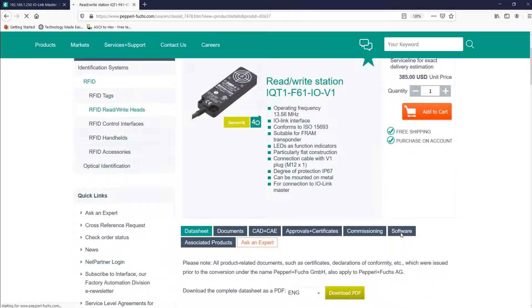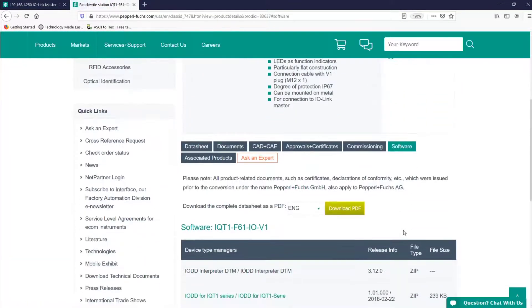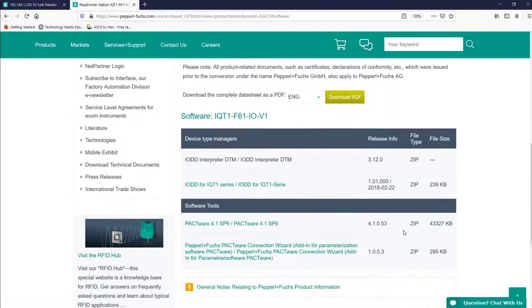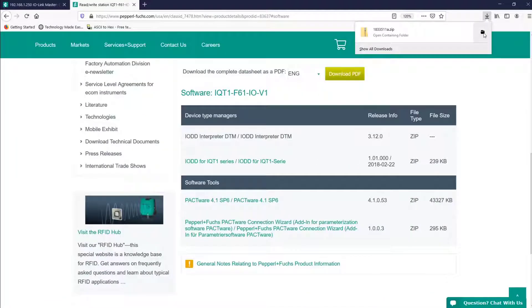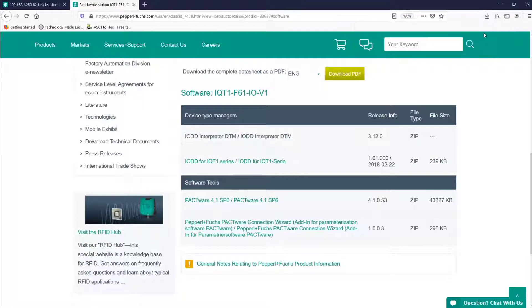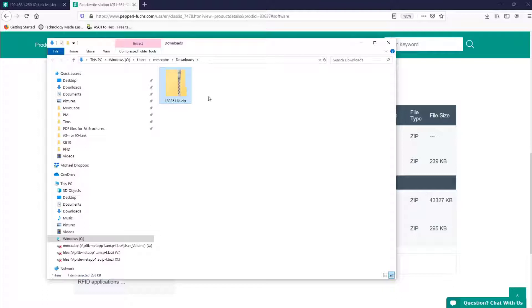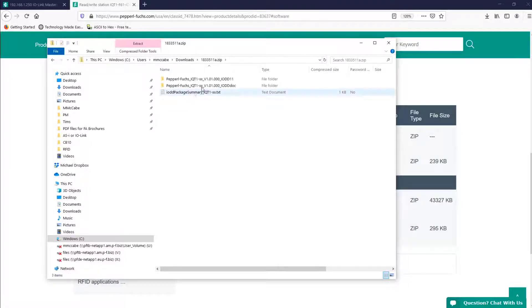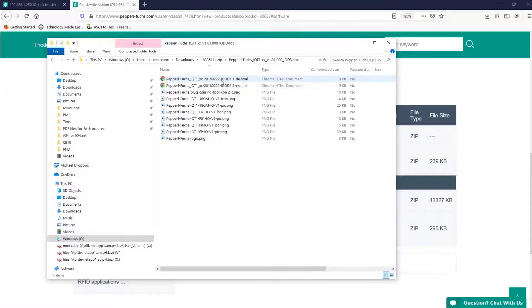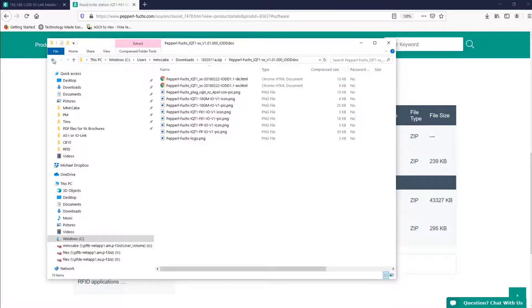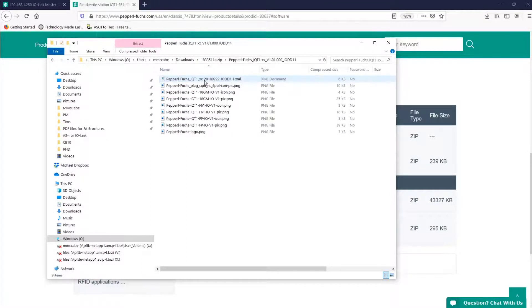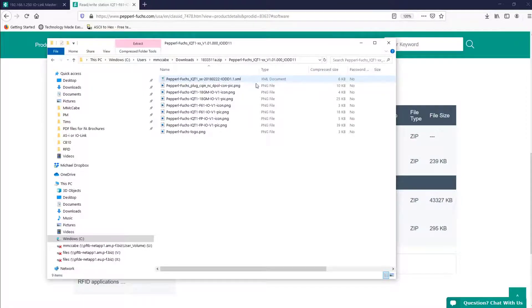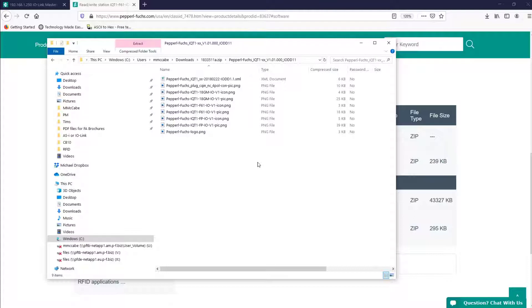Then let's go to software. I'll download the IODD for IQT1 series. And once done, I'll open it up. Here is the zip file that I just downloaded. Again, my device is version 1.1, so this looks good. Now the folder below provides us the HTML document, which I'll cover in the next video. And as I said before, each IO-Link device has an IODD file. But also know that one IODD file may contain multiple similar devices. In my case, each high-frequency IO-Link RFID head shown in an earlier video is covered by this IODD file.